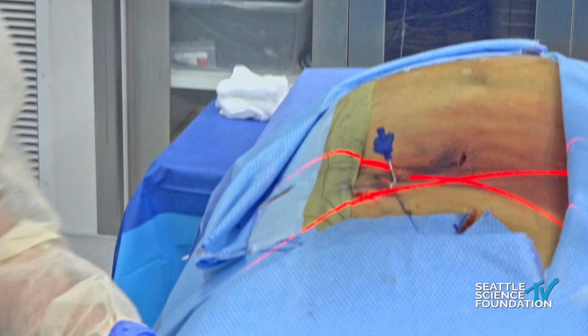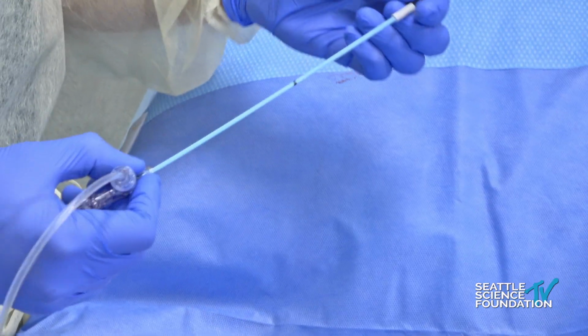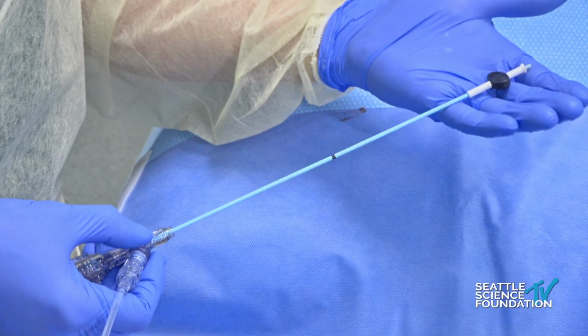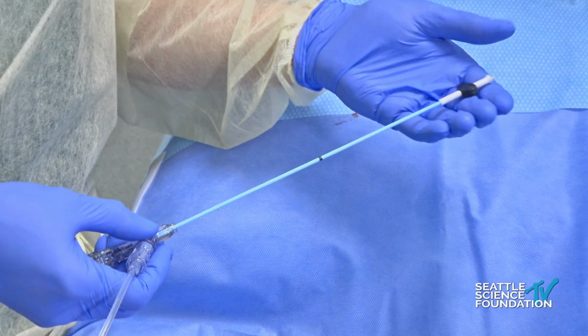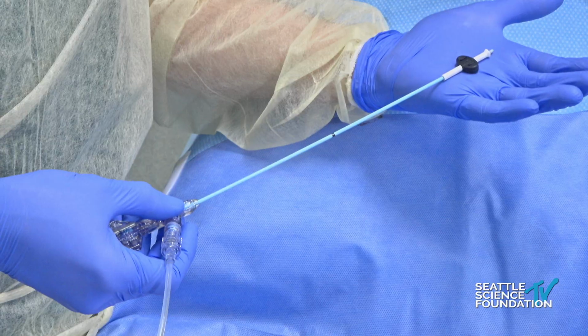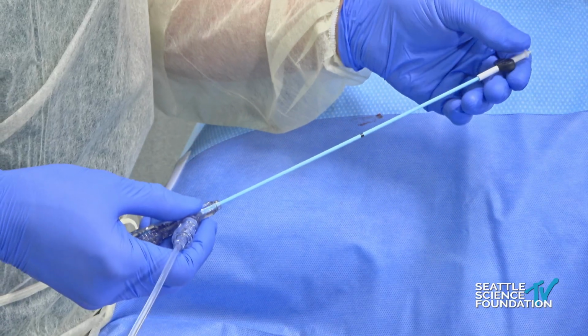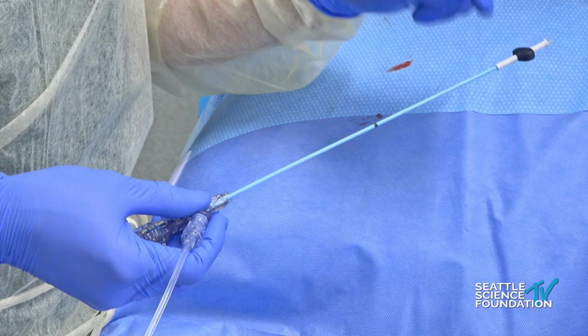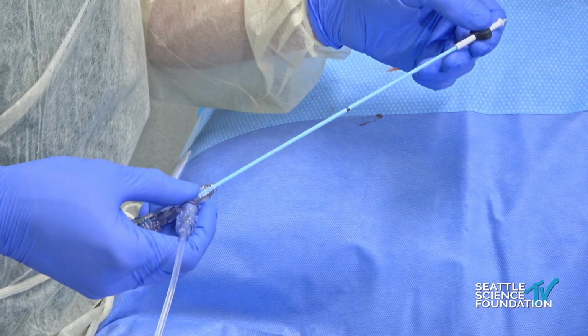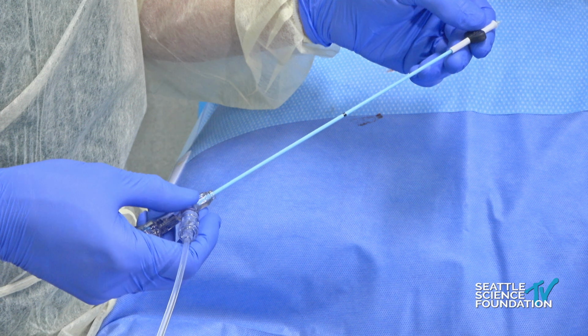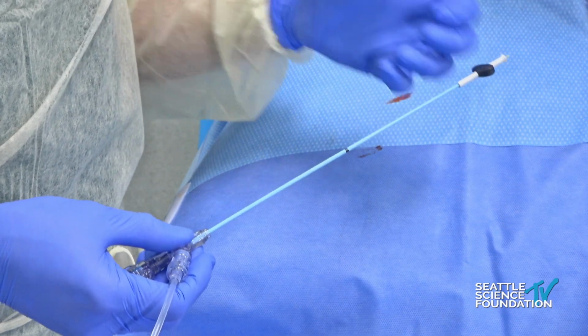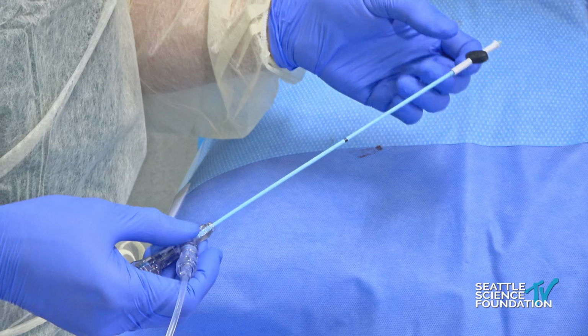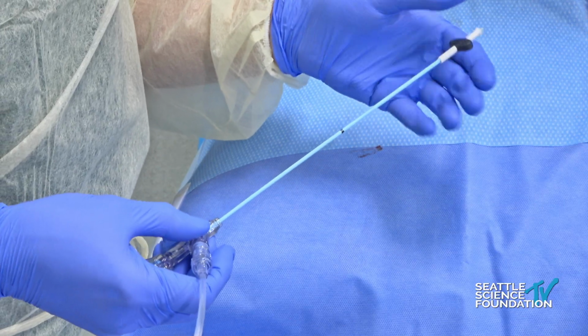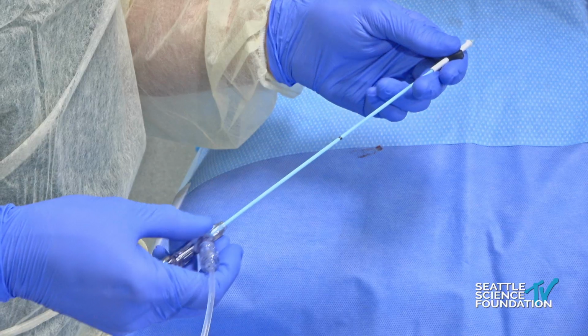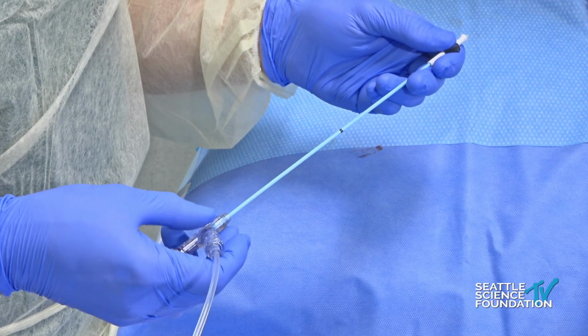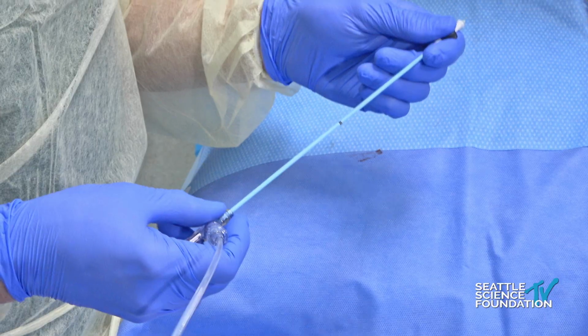And then there is normally a sheet that is covering the balloon that, in comparison to a lot of other medical devices, we just throw out. This one we want to keep because we can reuse this balloon for other levels, which is an important point. This is a balloon that has a low compliance and high pressure, so it can go up to 700 psi. Due to the low compliance, we can reuse it at multiple levels, which is a great asset to have if we want to do kyphoplasty at multiple levels.